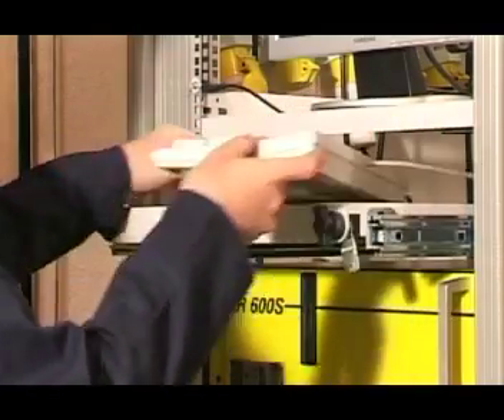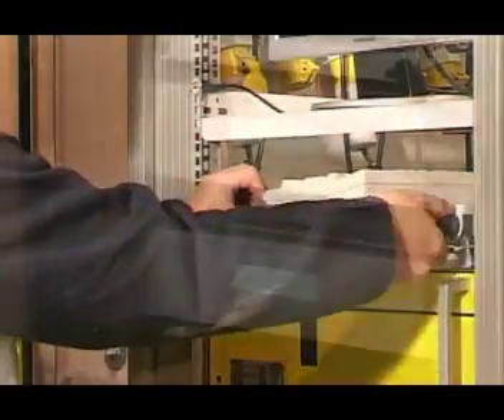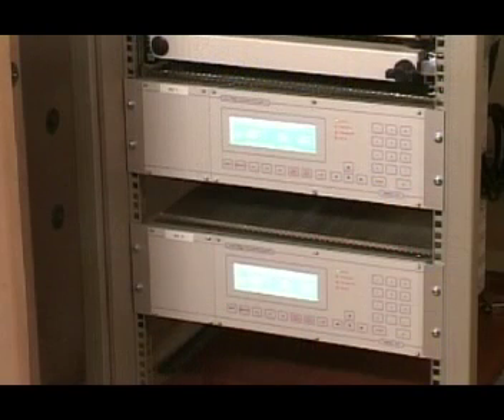And also in the bottom of this cabinet we decided to house the specialised equipment for measuring VOCs, which was a requirement of the new waste incineration directive to come into force in December. So the 2 machines here will give an output that will also be logged into our OPSIS system and presented to the user back in the control rooms.